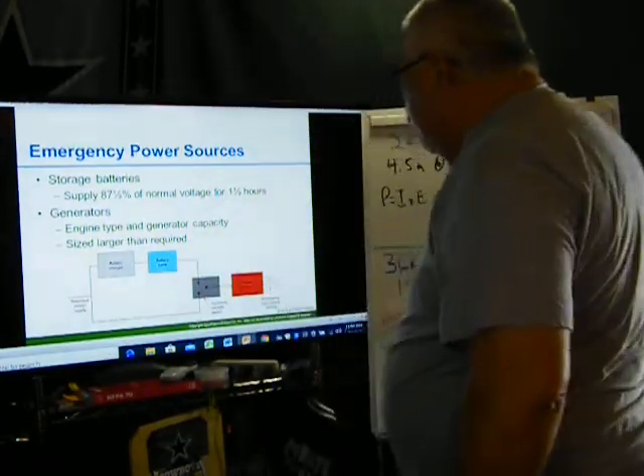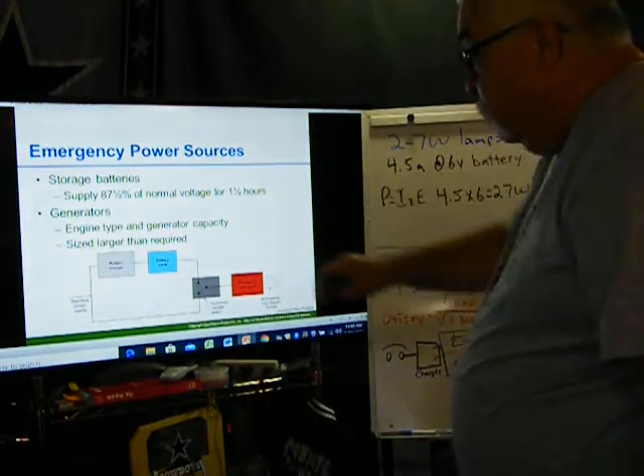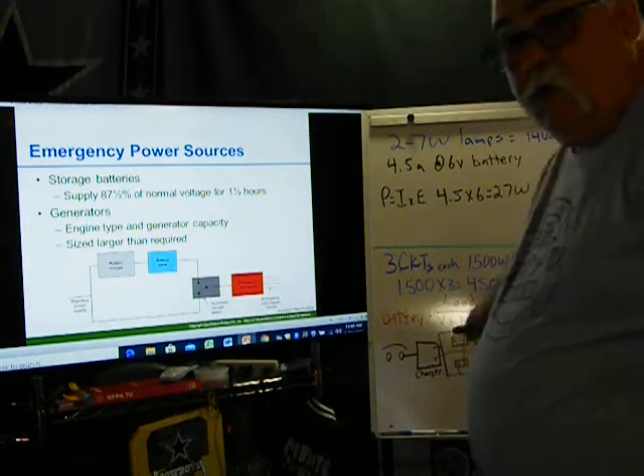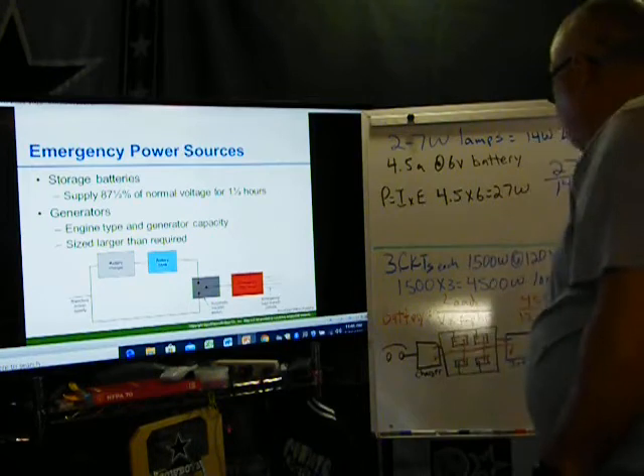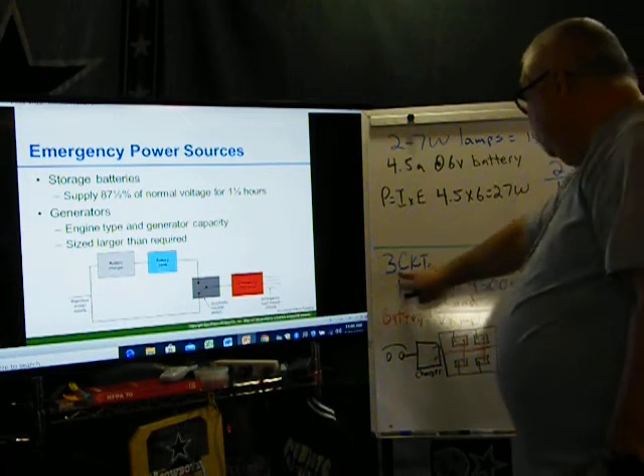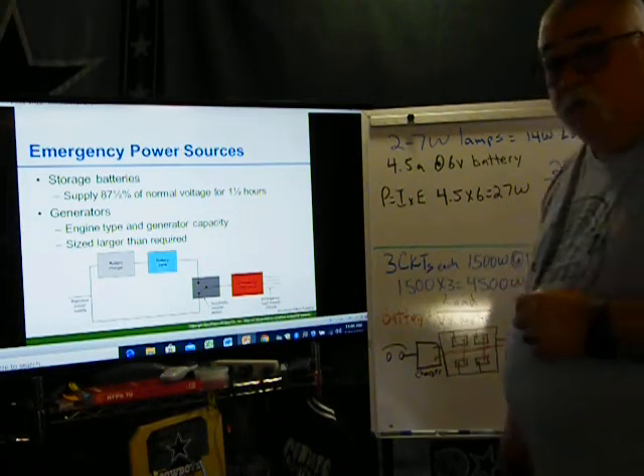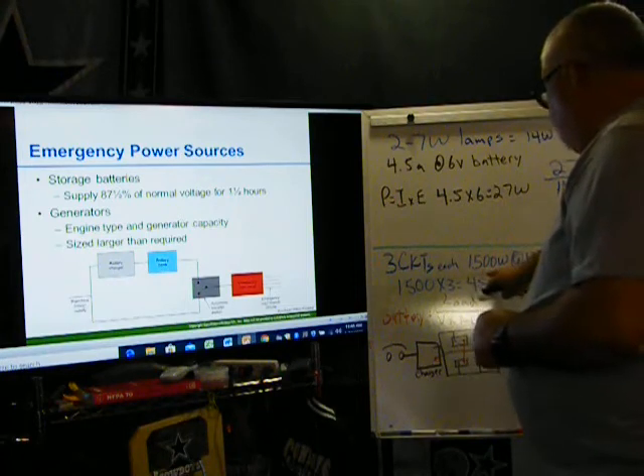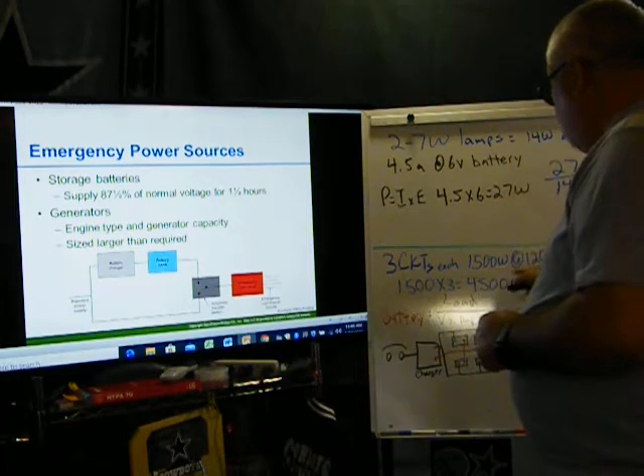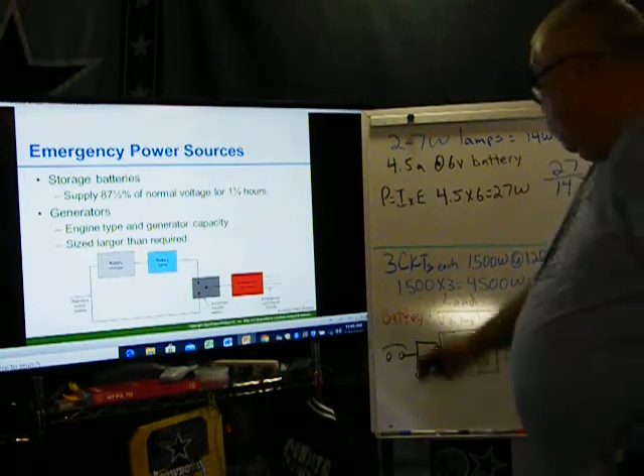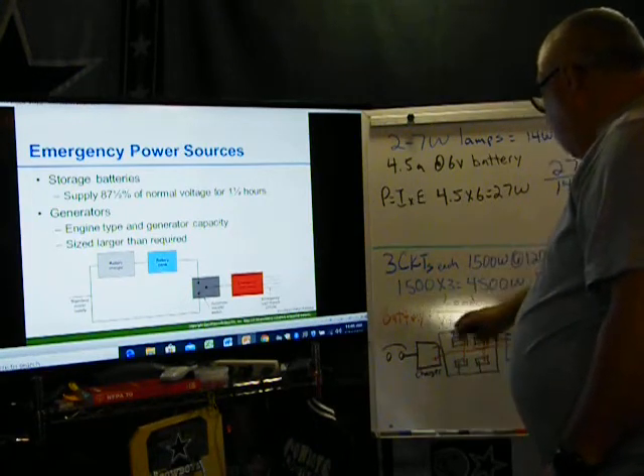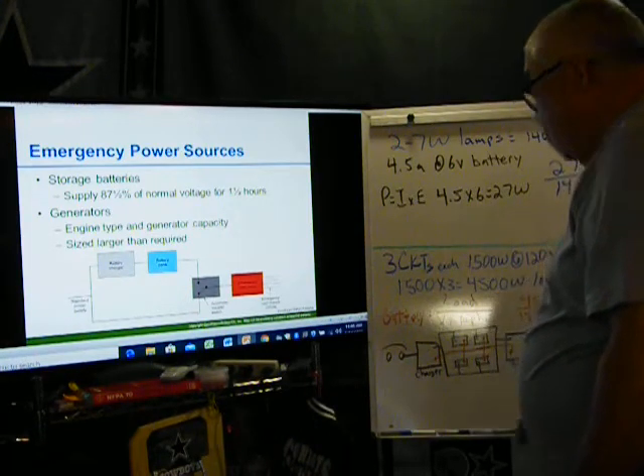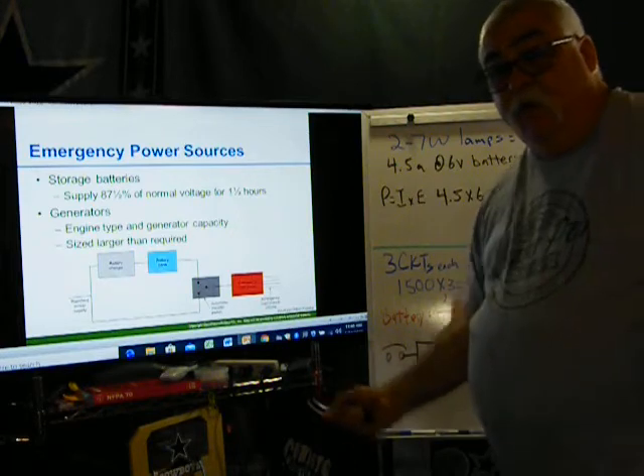Alright. So now I also did, I'm going to the battery. So you can see my drawing down here. So I got 3 circuits. So I have a total of 3 circuits that are coming off these batteries. They're 1500 watts, each one at 120 volts. So I get the 1500 watts multiplied by 3. So my total load is 4500 watts. How many batteries do I need?